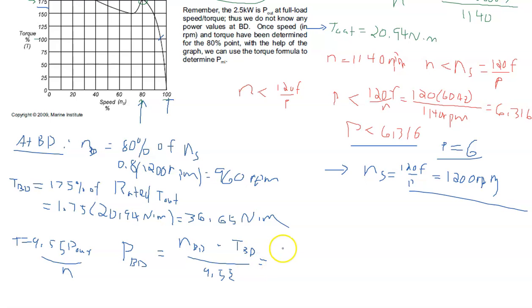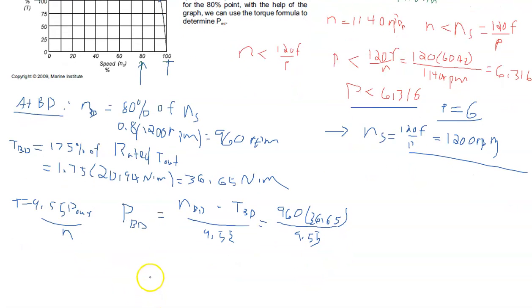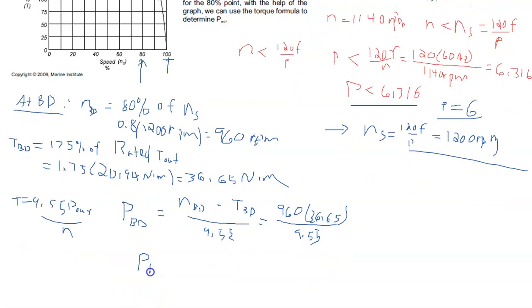So that is equal to 960 RPMs, the 36.65 Nm, divided by the constant 9.55. The power produced at breakdown will be equal to 3684 watts.